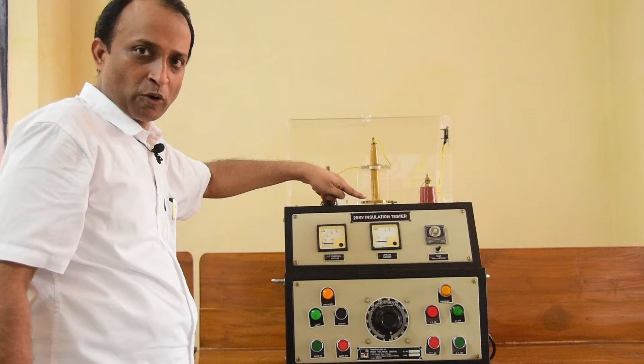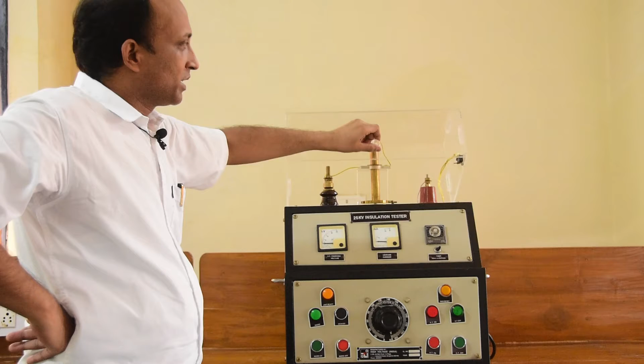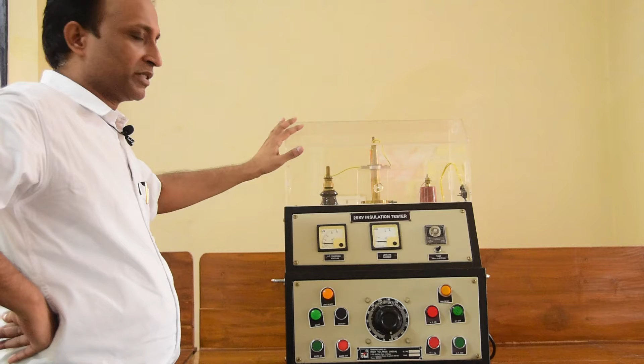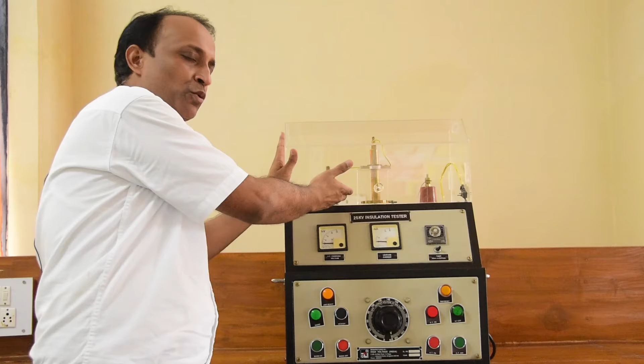Now apart from this control panel and this electrode assembly, there is a safety cover or safety shield provided on top of the assembly. This is a fiberglass assembly. Whenever we test the paper insulator, we keep the samples inside, right? And after keeping the sample, we apply the voltage and the sample will fail. In order to provide safety to the personnel who is working on this test assembly, this fiberglass cover is helpful. It will prevent any sparking or any fumes arising due to the failure of the solid insulator from reaching the face or maybe affecting the person who is working on it.